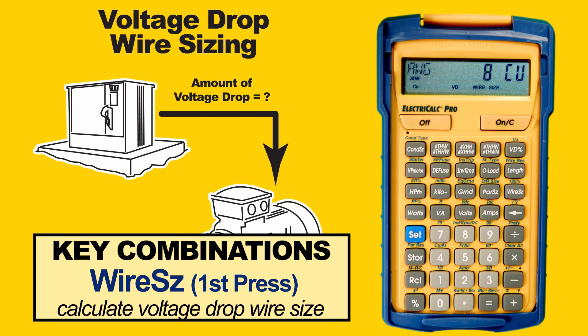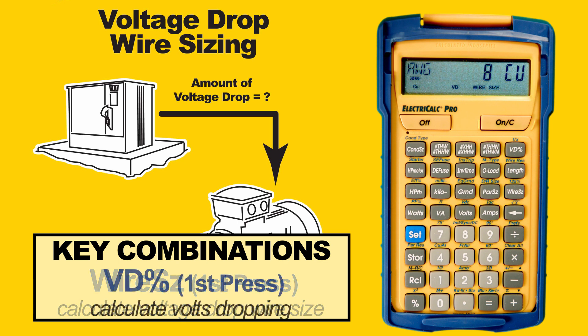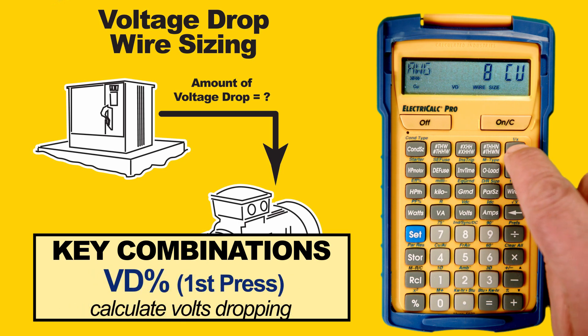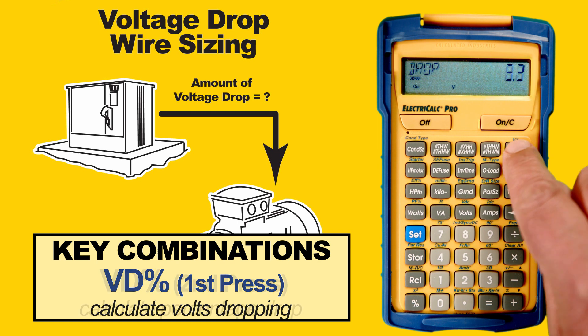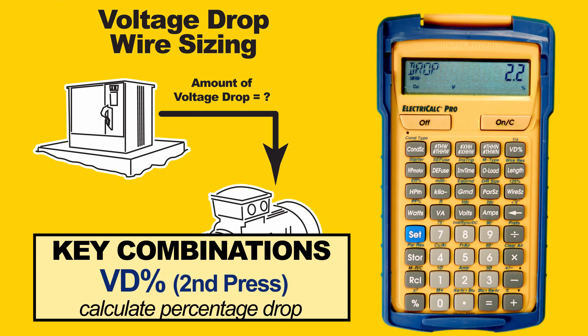Voltage drop is affecting that wire size. If I press the voltage drop key, it tells me that 5.3 volts are dropping. If I press it again, I see the percentage drop, which is 2.2%, which is well below my 3% maximum limit.